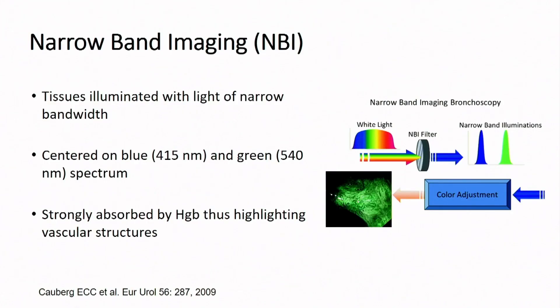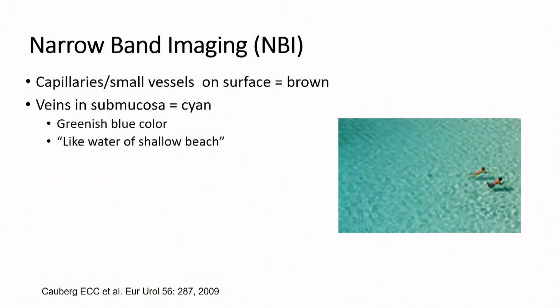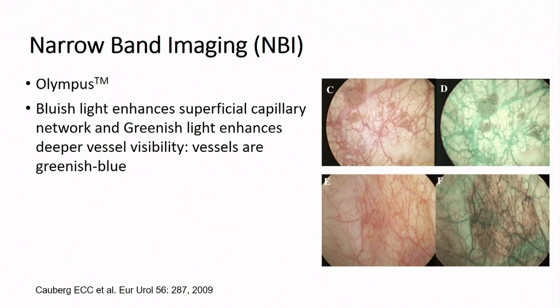Narrowband imaging takes advantage of the fact that tissues illuminate with light in a narrow band. If you focus on blue and green — the spectrum where hemoglobin is absorbed — you can highlight vascular structures. Tumors show up as brown structures on the surface, and the deeper blood vessel capillaries appear more green, like being on a shallow beach. This is what narrowband technology, which is proprietary through Olympus, provides.